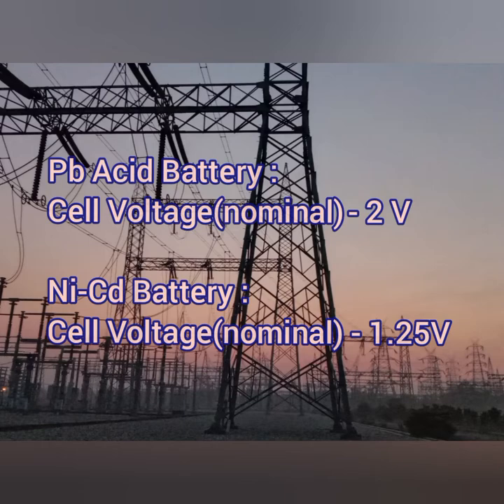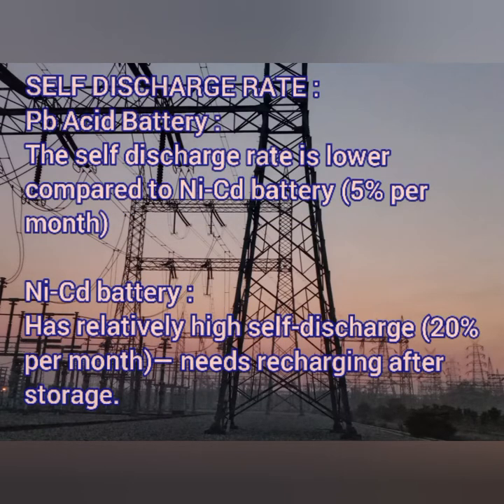This means that if an application requires 10 nickel cadmium battery cells, a lead acid battery would only require about 7 to 8 cells. However, even though lead acid has a higher cell voltage, the physical space per cell is much larger than nickel cadmium.